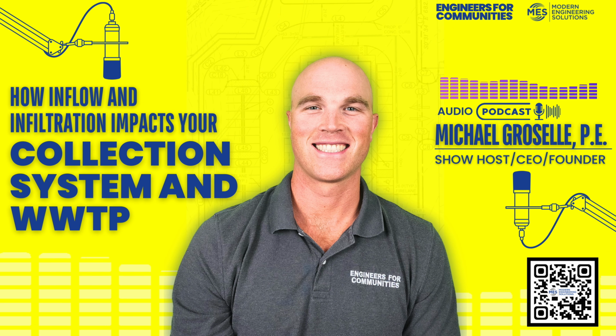If there's smoke coming out of a clean out to a home, it can identify that. If you've got issues with your manhole, so if your manhole is not super sealed, there'll be a bunch of smoke coming out of it. And like I previously mentioned, it helps to identify cross connections between the storm and the sanitary.